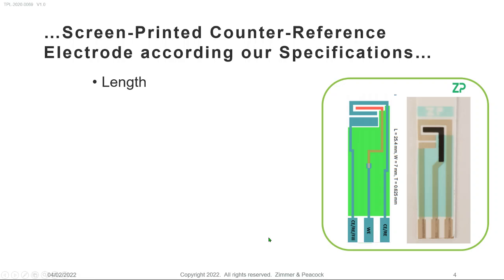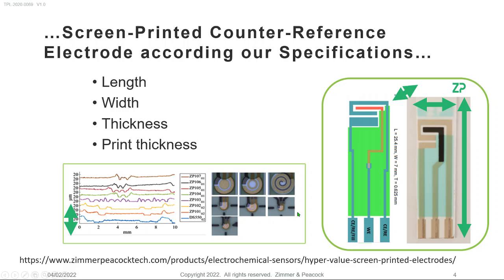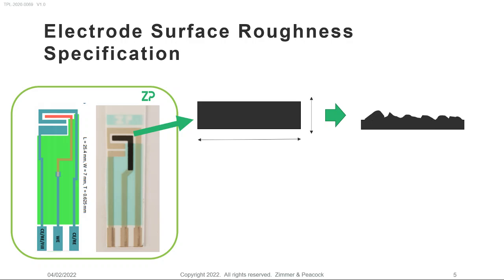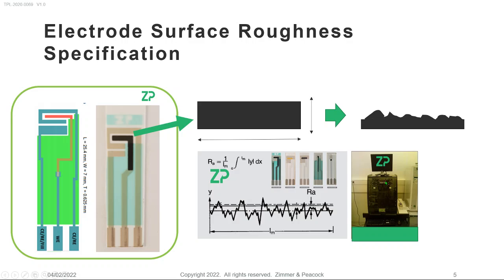When someone requests a screen printed electrode, the first thing that comes in is a request with gross dimensions — certain length, width, thickness, print thickness. What is rarer is that people come in and specify electrode roughness. That's OK because it can be measured, but we have seen situations where people switch from one manufacturer to another and, though everything is grossly the same, the electrodes have different roughnesses, so sensitivities or baselines all jump up.